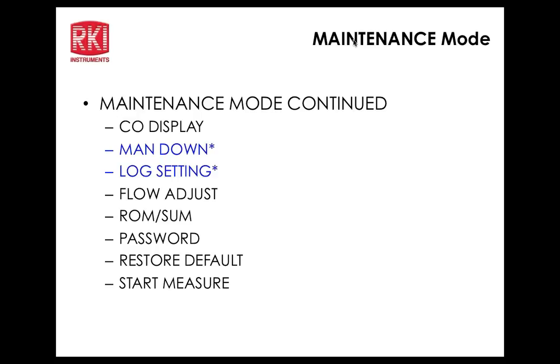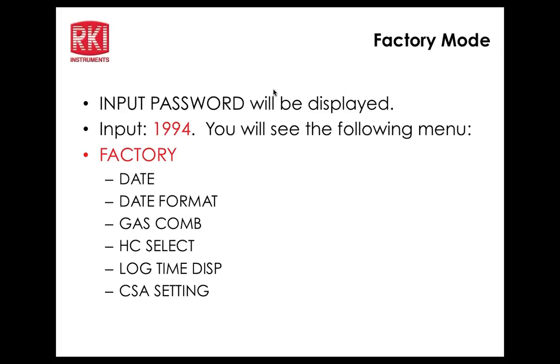How long do you have to hold those two buttons before you get that change in the screen? It's about 5 seconds, longer than the 2012. So here you can see now we're in leak check mode, full scale 5,000 ppm.